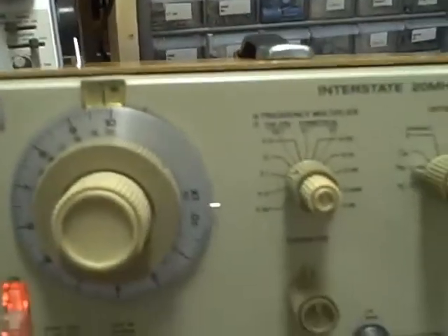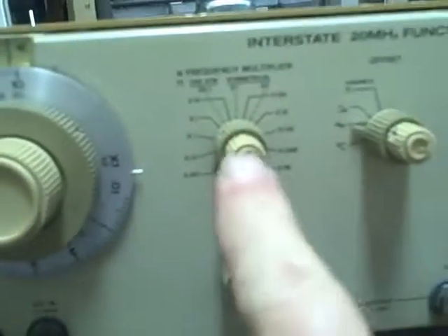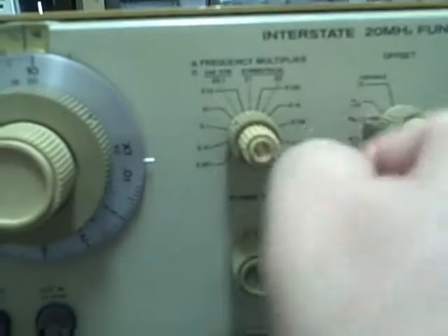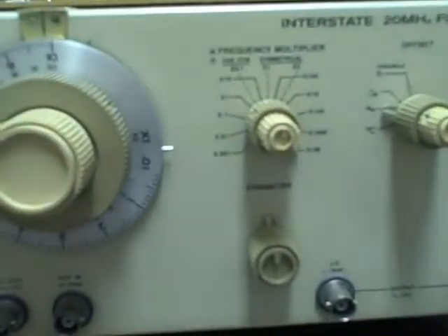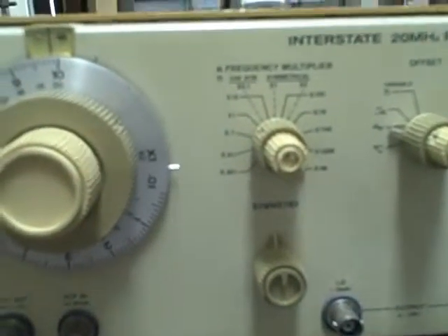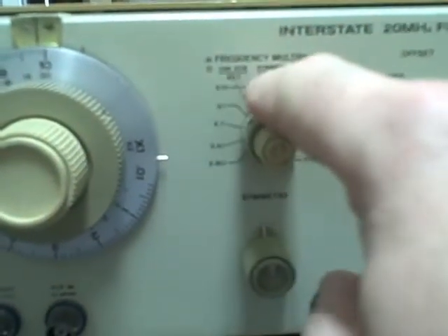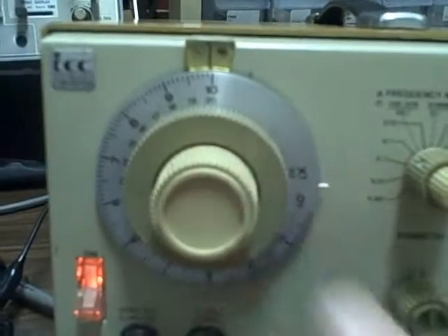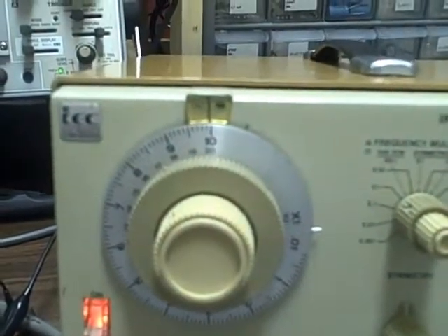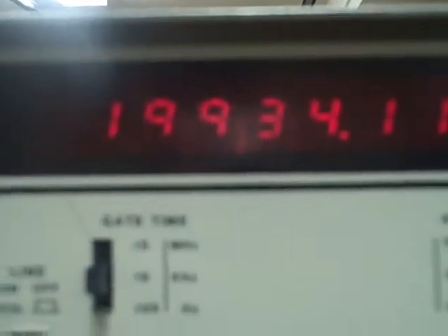So if you rotate this center dial here, right now I'm in the ×1 position. I could go to the left, that'd be ×1/10. If I go to the right, it's ×2. It tells you on the scale up here, 0.1, 1, 2.